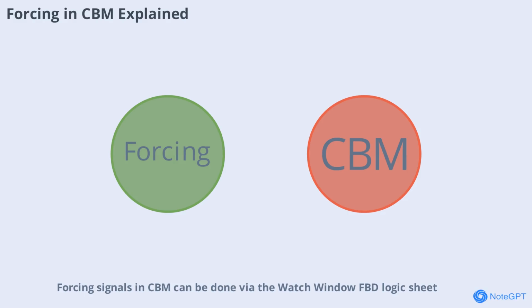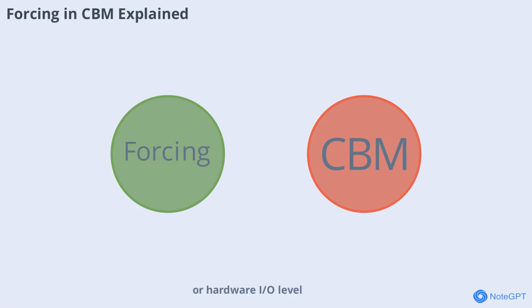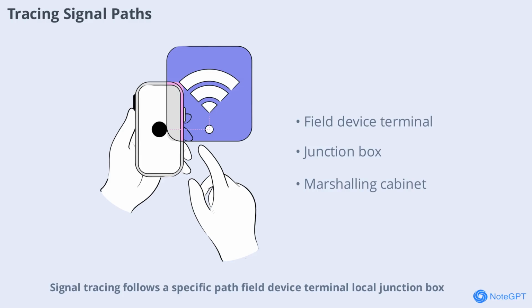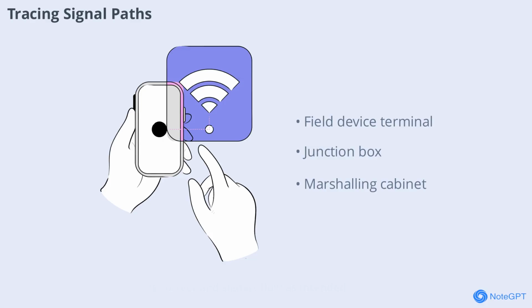Forcing signals in CBM can be done via the watch window, FBD logic sheet, or hardware I/O level. Forces survive a warm restart but are cleared during a cold restart. Understanding these methods is essential for effective commissioning and troubleshooting. Signal tracing follows a specific path: field device terminal, local junction box, marshalling cabinet terminal strips, S800 module terminal base, and software channel in CBM. This process ensures that every connection is correct and signals flow as intended.